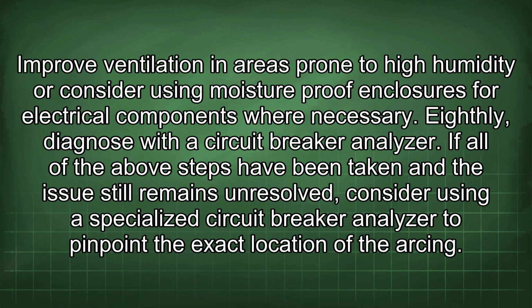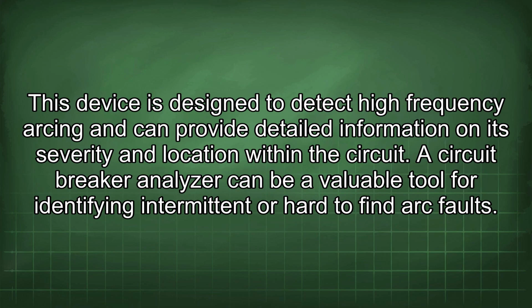Eighthly, diagnose with a circuit breaker analyzer. If all of the above steps have been taken and the issue still remains unresolved, consider using a specialized circuit breaker analyzer to pinpoint the exact location of the arcing. This device is designed to detect high-frequency arcing and can provide detailed information on its severity and location within the circuit. A circuit breaker analyzer can be a valuable tool for identifying intermittent or hard-to-find arc faults.